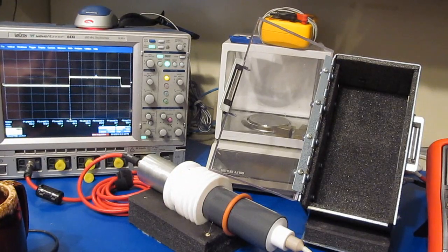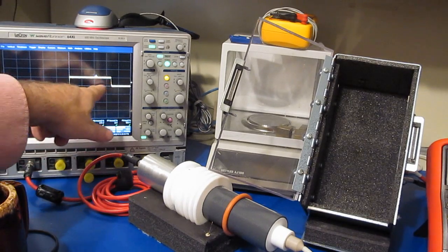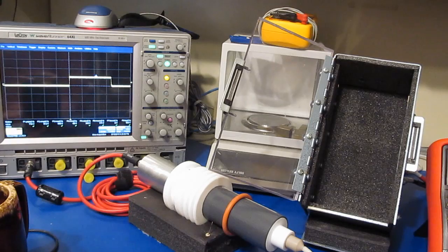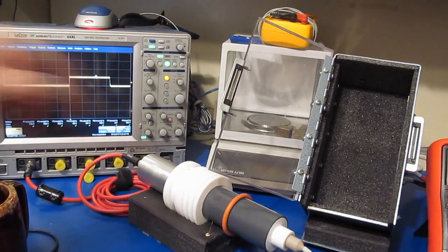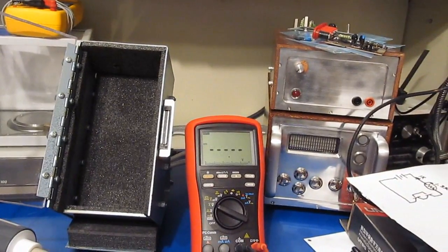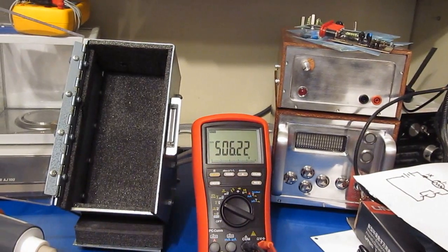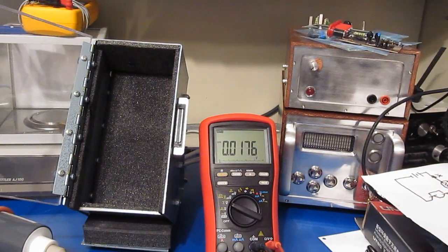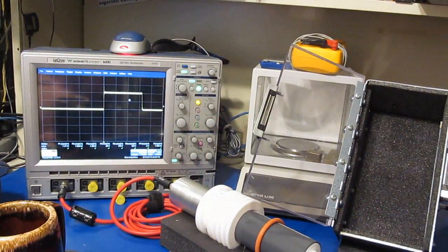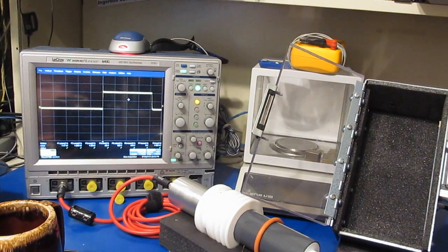So when I pulse this, this is 100 milliseconds per division, so this is 0.3 seconds or 0.5 seconds here. And if we look with the Brymen, you can see it's basically 500 volts. So what I'll do is turn up the power supply a little higher, and there you can see we're at roughly 1000 volts, now 2 divisions up.